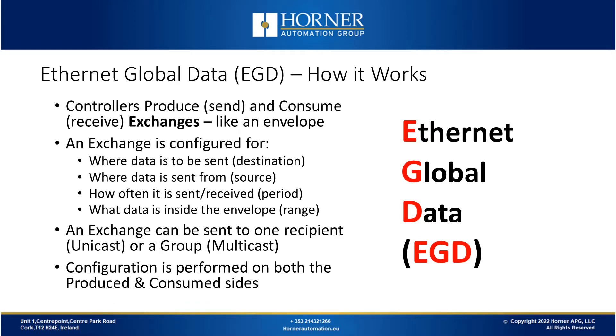With EGD, controllers produce (or send) and consume (or receive) what are called exchanges. You can think of those like an envelope. An exchange needs to be configured for where the data is to be sent or its destination, where the data is going to be sent from or the source, and how often the data is going to be sent and received. It must also be configured for what data is going to be inside the envelope, which is called the range. An exchange can be sent to one recipient, which is a unicast, or to multiple recipients, which is called a multicast. Configuration is required on both the produce and the consume side.